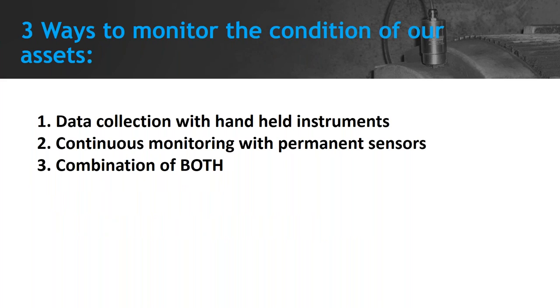We view it as three ways to monitor the condition of your assets. One is pretty traditional — going out and doing handheld data collection with one of our Ultraprobe or grease caddy instruments, taking DB levels and WAV files and trending them over time. Another way is continuously monitoring with permanent sensors. Probably the best approach is using a combination of both — there's still a place for monthly route-based data collection, and certainly a place for continuous monitoring as well.